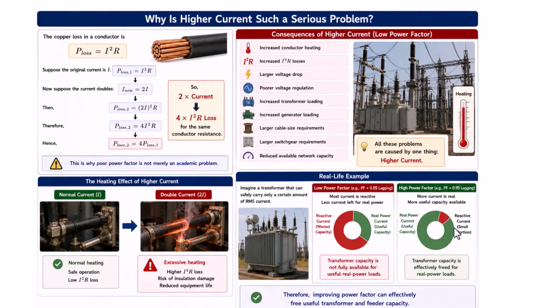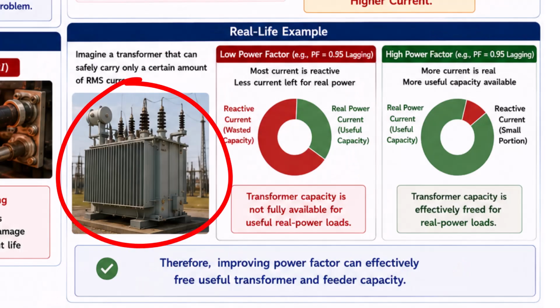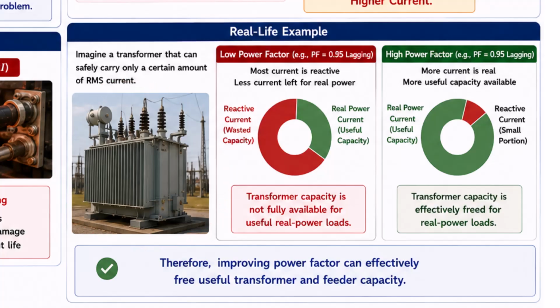Let's consider a transformer that can safely carry only a certain amount of RMS current. If a large portion of that current capacity is occupied by reactive current, less current capacity remains available for additional real power loads. Therefore, improving power factor can effectively free useful transformer and feeder capacity.